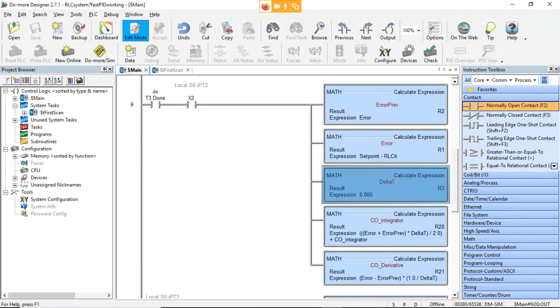blow up your whole PLC like you saw me do, and then I had to stop the PLC. I had to basically reboot the entire PLC, right? Like if we were doing this on the real PLC and it came up with that not a number, we would have to power the thing off and then back on again to reset it, because it was just hosed at that point.